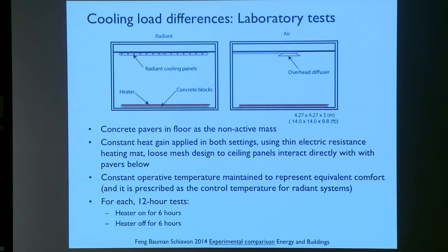I'm just showing you one example here where we looked at testing some of these traditional methods of calculating cooling loads. We did it in a lab where we could have either radiant cooling panels on the ceiling or diffusers. On the floor, we had non-active mass using concrete pavers, and we simulated heat gain with a mesh heating mat - it was mesh so the radiant ceiling could interact with those concrete blocks.